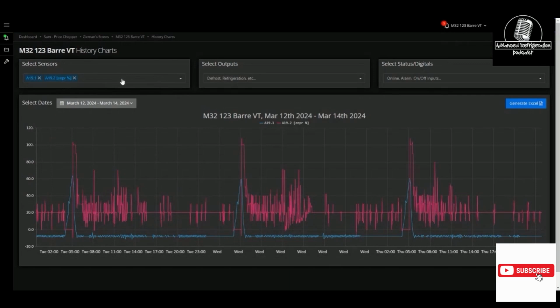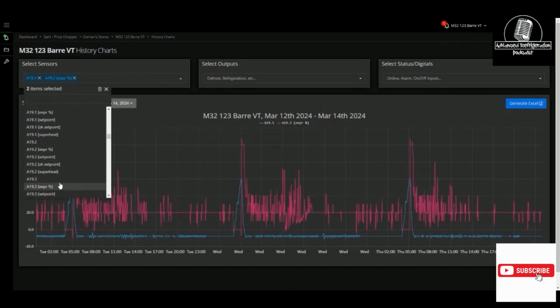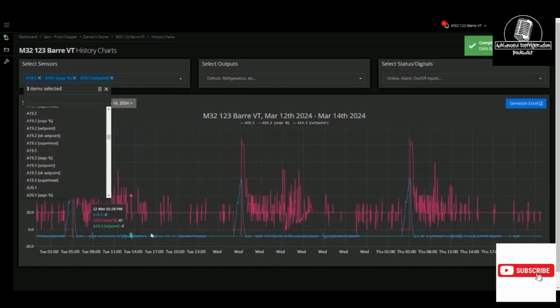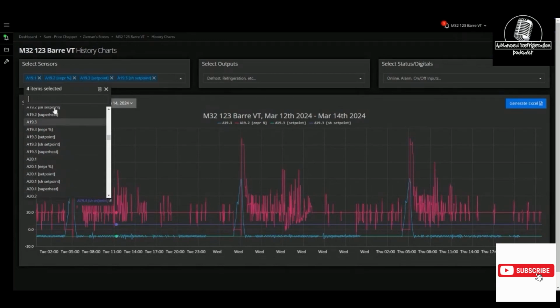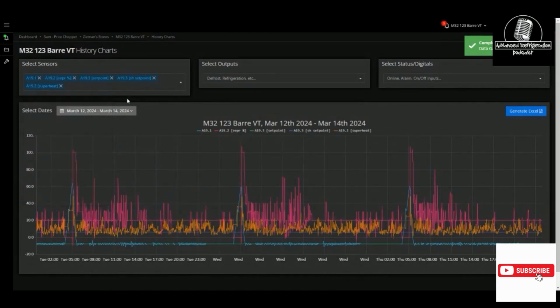I can pretty much take any output that's in, this is a Dixell. So this is an XM679K controller. I can see the set point, overlay the set. So obviously it stays right at set point pretty well. I can see the superheat set point, and I can overlay all this together. There's the actual superheat all under one graph.